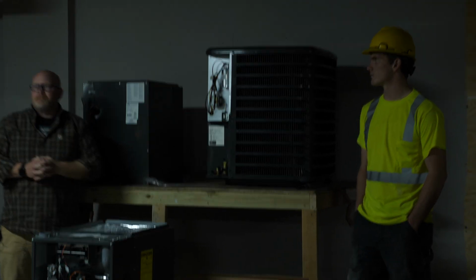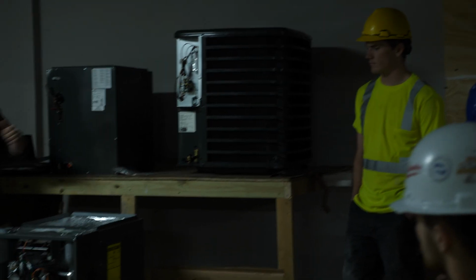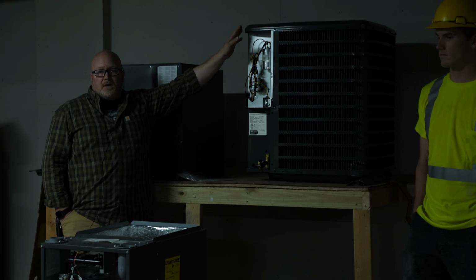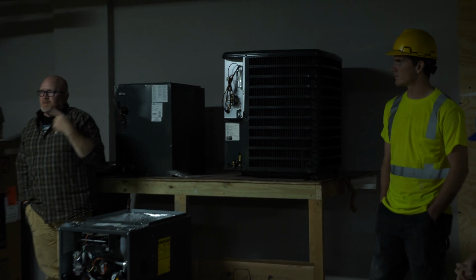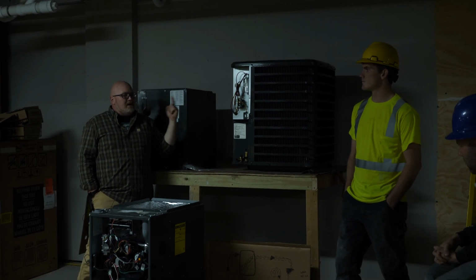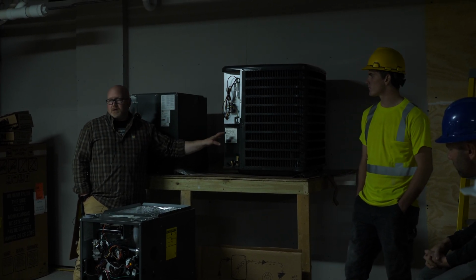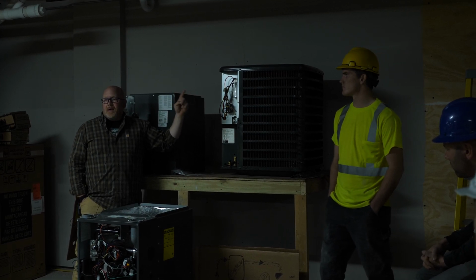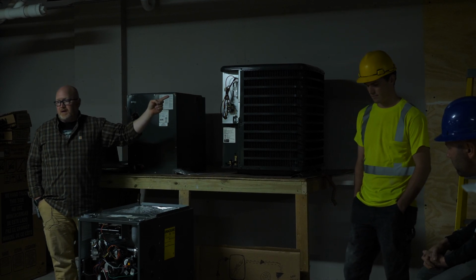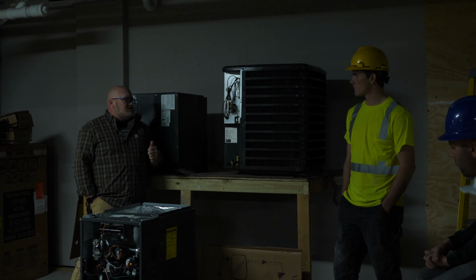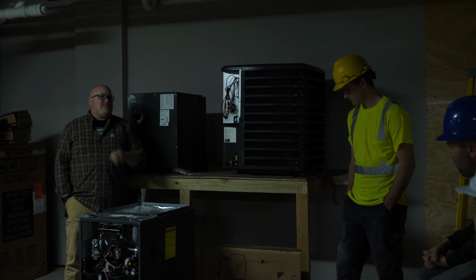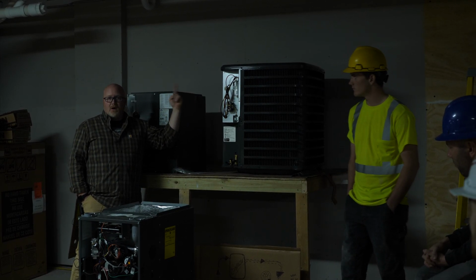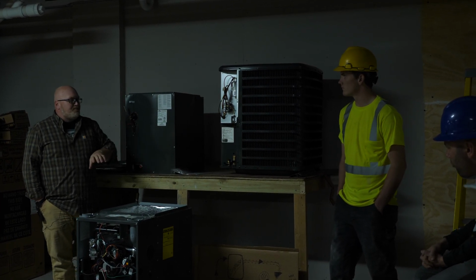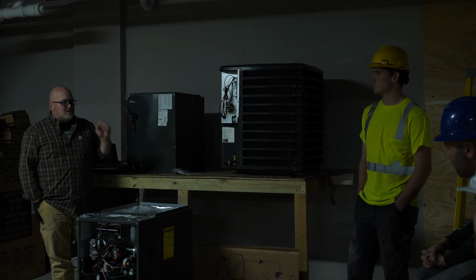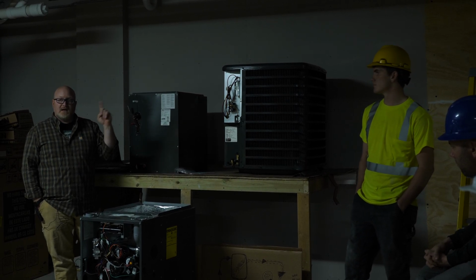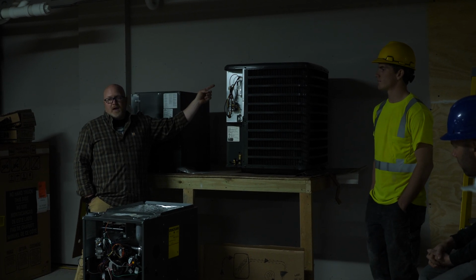So number 1, contactor. Number 2, your capacitor. Number 3, this one is also fairly common. On top up here, we talked about how the warm air gets rejected from the compressor condenser. So up on top here, you have a fan, a set of blades, and that fan runs on a motor. And so if you go outside, you're not getting cold air, but you can hear the compressor running, but you've got no heat coming off the unit, that's telling you that your condenser fan motor has failed. Your condenser fan motor, unfortunately, most of them are not interlinked with the compressor. So what that means is the condenser fan motor could fail, it could stop running, but your compressor could continue running. So it's a pretty easy observation. As long as your air conditioning is on and you hear that compressor running, but that condenser fan motor is not spinning, then you've got basically a condenser fan motor that gets replaced.